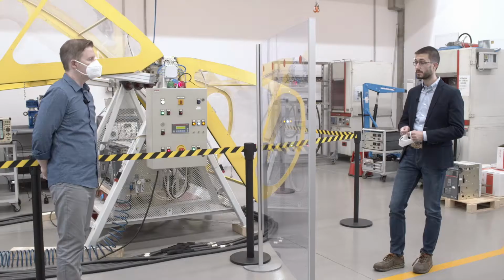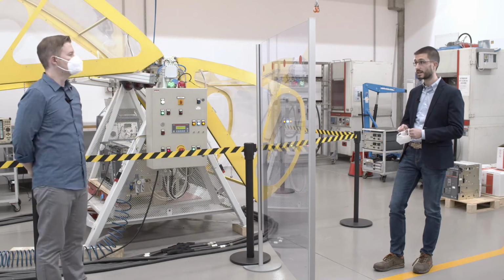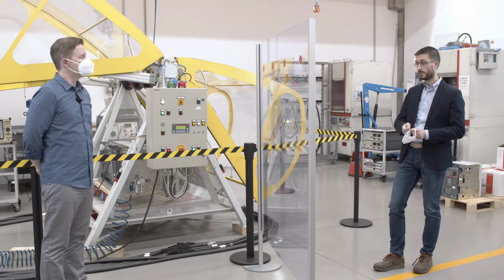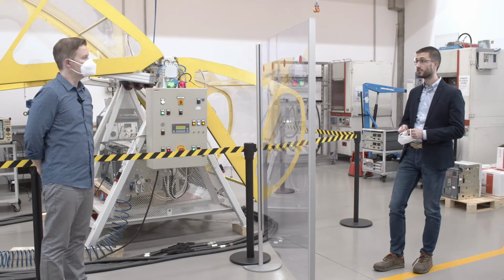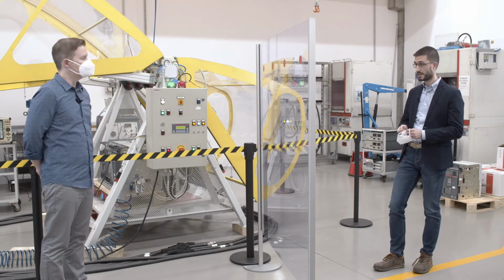On the other end is a 4000 amps circuit breaker, Emax 2, which is under certification now for 100 kA, again at the rated voltage of 1500 volts DC, both short circuit breaking capacity, but even withstand current. And even if we said about the generation spread, smaller plants, the power that can be switched by this breaker is really significant. So, does it mean that even for DC test capability are increasing?